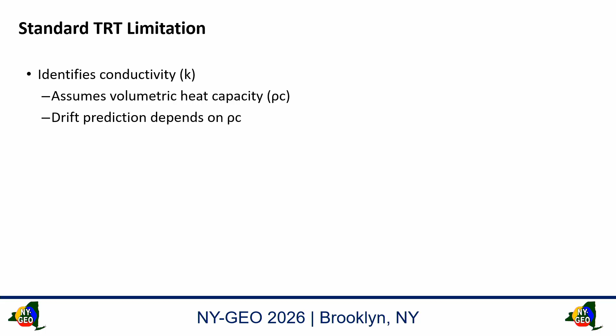So what I call advanced thermal response testing does measure the conductivity and far field, but it further measures the volumetric heat capacity. To do that, I have to calibrate a digital twin and model it. This allows me to reduce the uncertainty on the values and operations of these systems. That's kind of new.